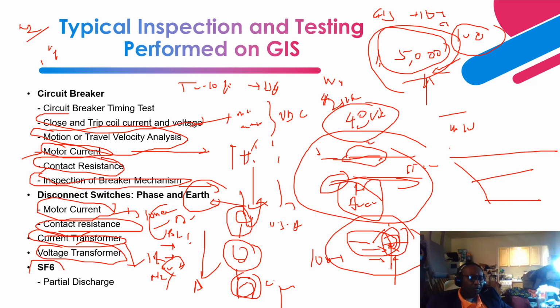Then for the SF6 gas, PD activity, especially when you have a contaminated environment, then PD becomes a problem for you to fight. And also if you have leaking SF6 gas, that is when the elements of the weather, moisture and all those things, intrude into the SF6 that is in that enclosure, and basically can create PD activity.